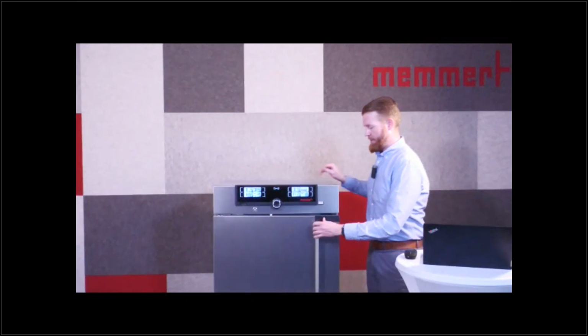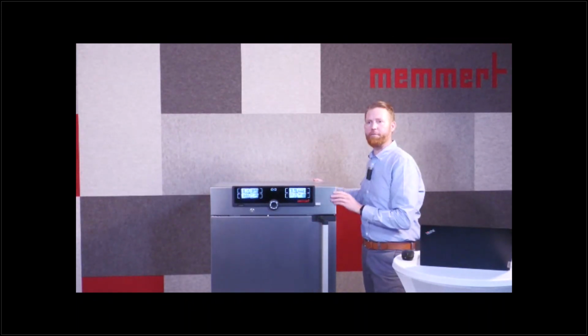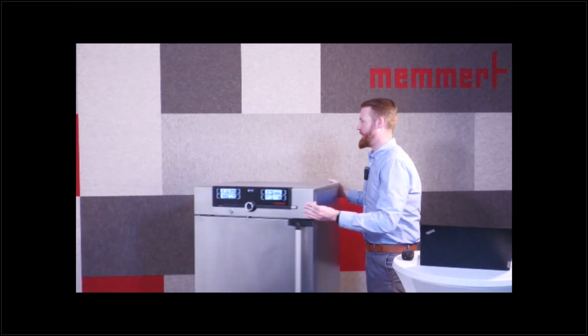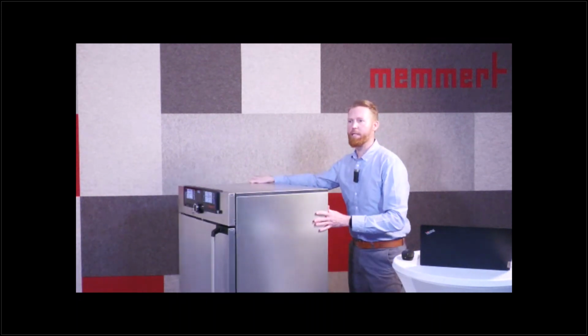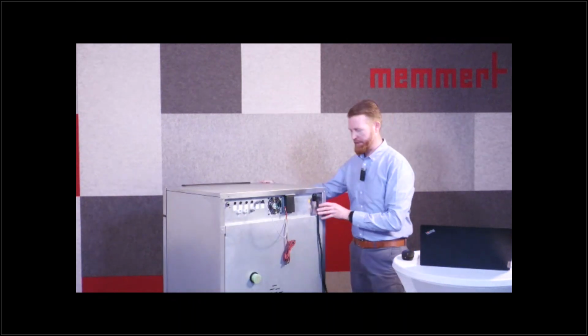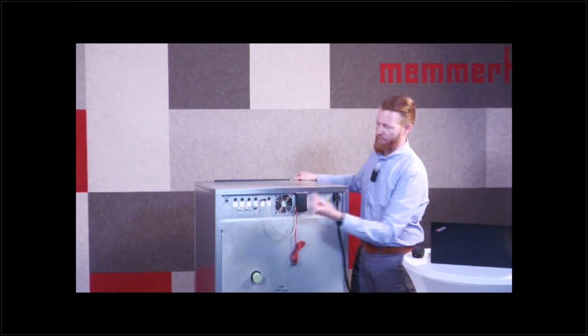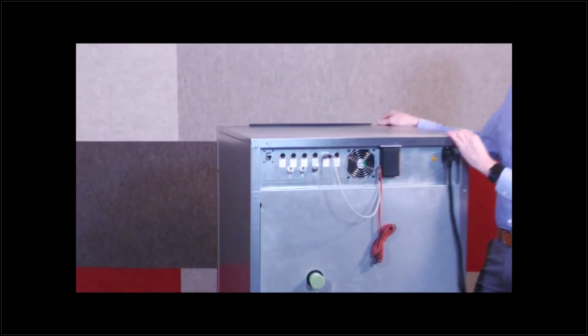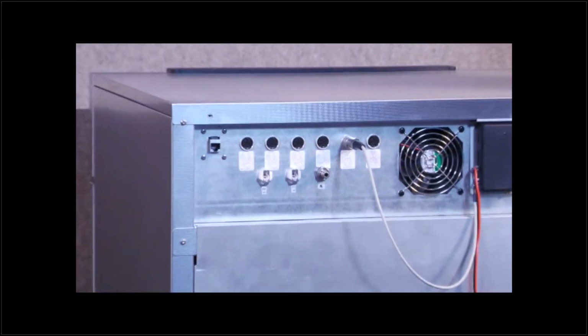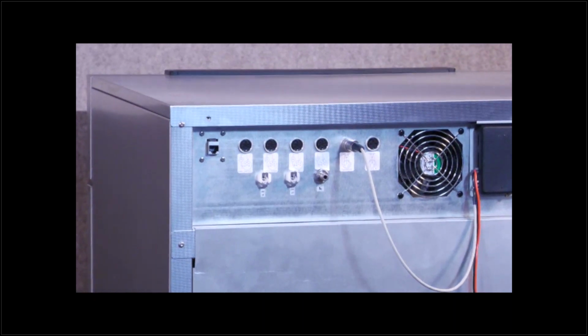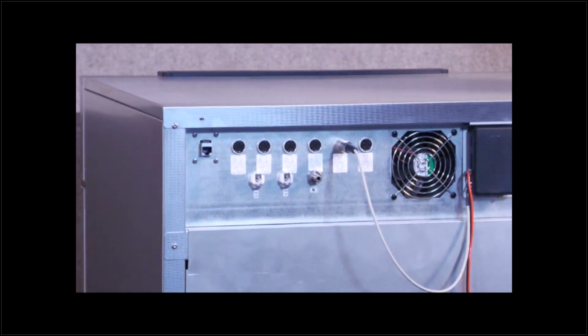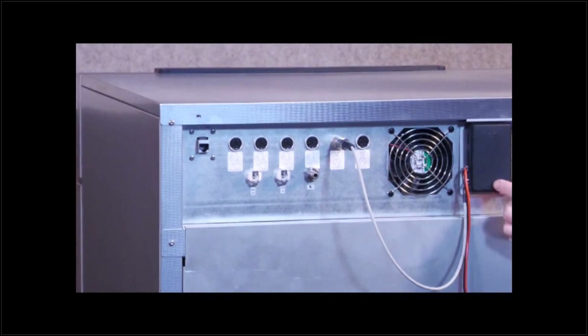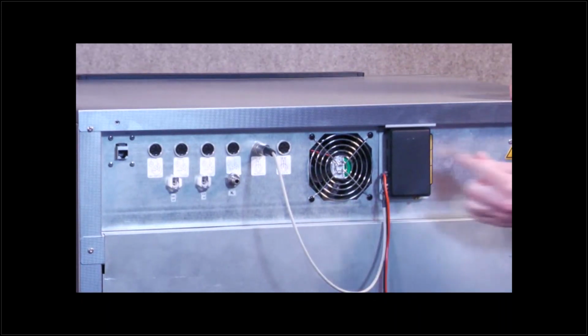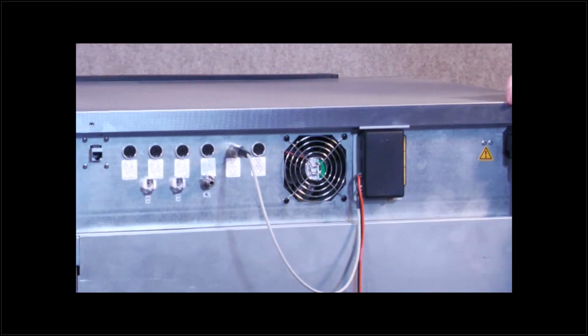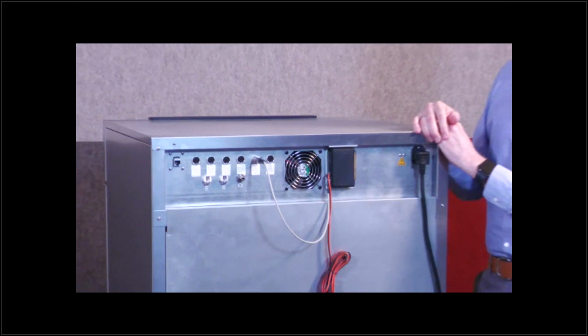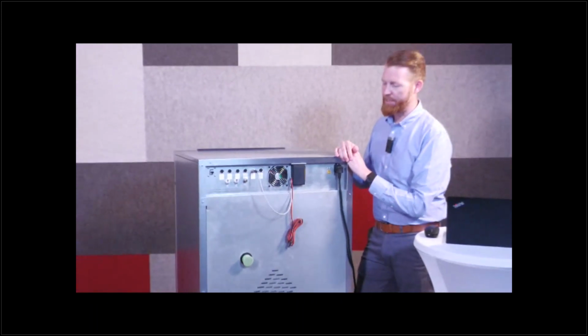Safety features. Of course, there are standard safety features coming with the device, but we also have talked about additional safety features. I'm just turning the incubator here to show you some additional interfaces which are available, just to make sure that all the alarm messages are recorded and probably given to another monitoring system. Here we have a so-called mobile alert box. These boxes are offered by many manufacturers to receive alarm messages on your mobile phone if desired.